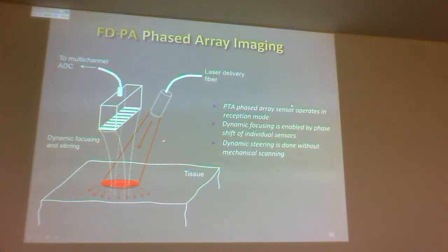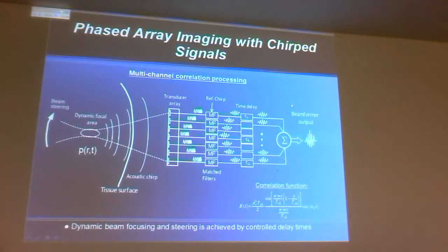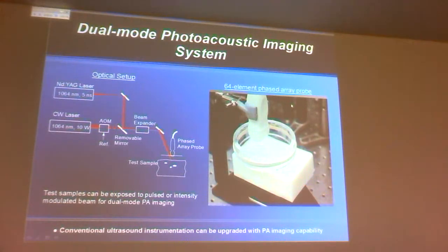So these are the transducer arrays. The light goes in, and then you pick up the information from the transducer array. This is a phased array, so as was explained in the morning, and I don't really need to say that anymore, you pick up information from different parts of the absorber, because simply this wave takes a longer time to get to the transducer than this wave, so you have to do dynamic beam focusing and steering, so that all of these waves are going to come in time. You see, all of them are formed together, so eventually they're going to come together here. So you can enforce the absorption that comes in from the medium. So all of that, all these transducer array issues are there. There is no difference here.